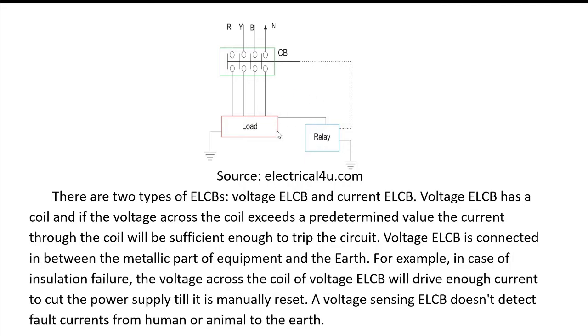So this is the circuit diagram of voltage ELCB. Voltage ELCB has a coil, and if the voltage across the coil exceeds a predetermined value, the current through the coil will be sufficient to trip the circuit. Voltage ELCB is connected in between the metallic part of the equipment and the earth. For example, in case of insulation failure, the voltage across the coil of voltage ELCB will drive enough current to cut the power supply till it is manually reset. A voltage sensing ELCB doesn't detect fault currents from the human or animal to the earth. This is about voltage ELCB.